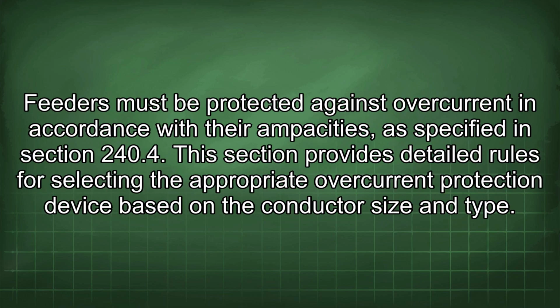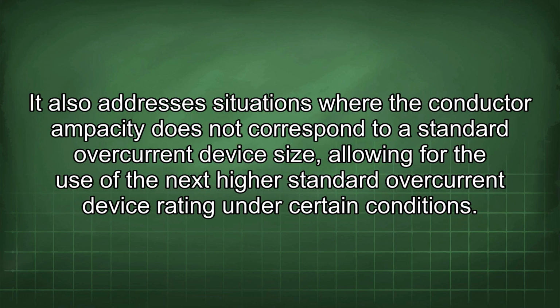Feeders must be protected against overcurrent in accordance with their ampacities, as specified in Section 240.4. This section provides detailed rules for selecting the appropriate overcurrent protection device based on the conductor size and type. It also addresses situations where the conductor ampacity does not correspond to a standard overcurrent device size, allowing for the use of the next higher standard overcurrent device rating under certain conditions.